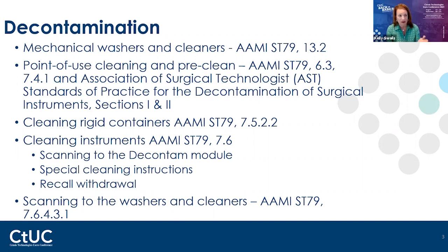Are they being cleaned? Now I see some facilities that are cleaning them inside that basket with disinfectant wipes. So Sani-Cloth is a common one I see, or they're cleaning them with alcohol. And what concerns me is that when that residue dries, you think, okay, it's fine, it dried. But when it goes in that sterilizer and that steam hits it, you're now making that dried residue fluid again. So is it ending up on our instruments? What's it doing to the instruments? If it's on the instruments and now you use them in surgery, maybe it has dried, but then you've got blood and saline that's going to reactivate that again. And so what is that chemical doing to tissue or organs?